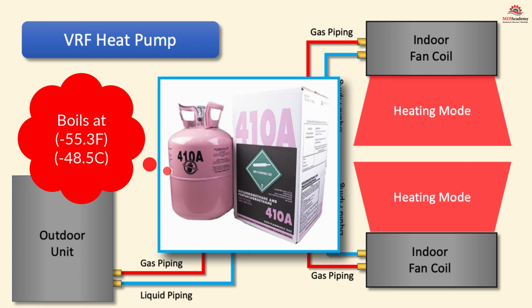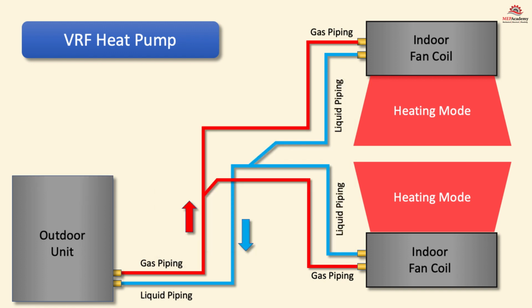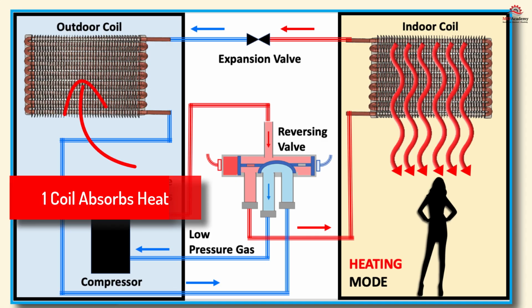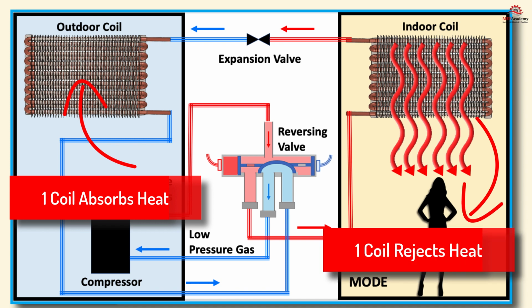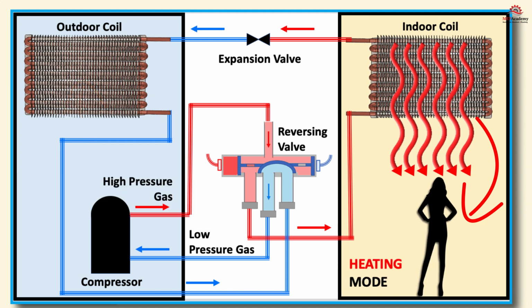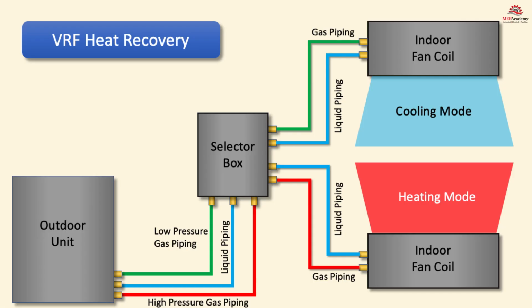That means this refrigerant circulating in the VRF system can still absorb heat from the cold outdoors and send it to the space to be heated. See our video on how heat pumps work for a better explanation. So it's easy to remember. One coil absorbs heat, takes it in, and the other rejects heat, throws it out, all with the magic of refrigerants. A much better and more efficient use of the heat being removed is to use it for some purpose, such as for a room needing heat while another zone is in cooling mode. This is what a heat recovery system is good at.